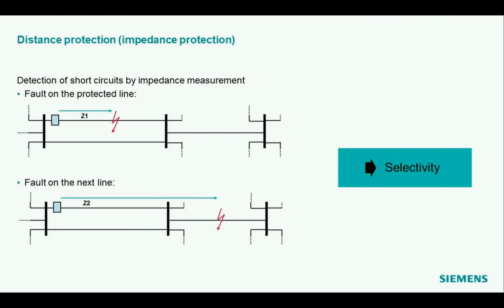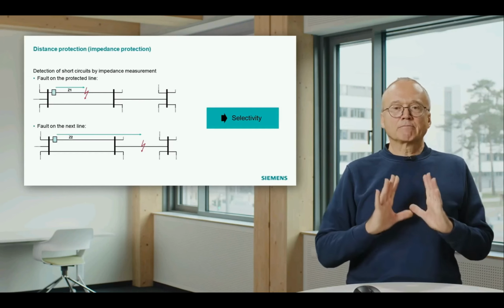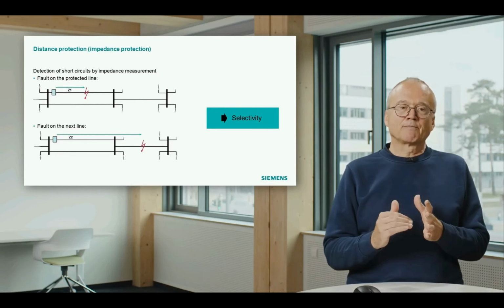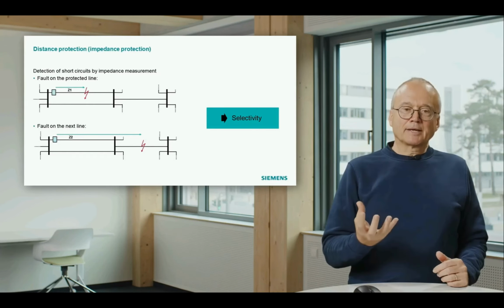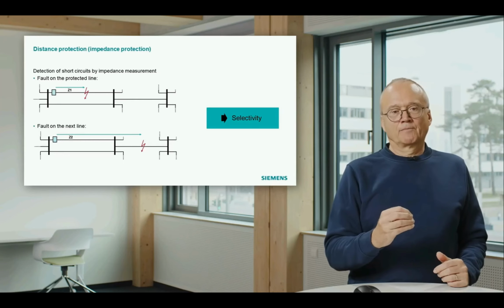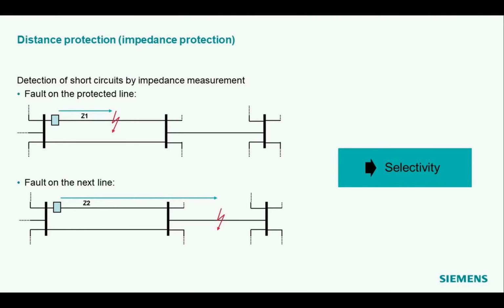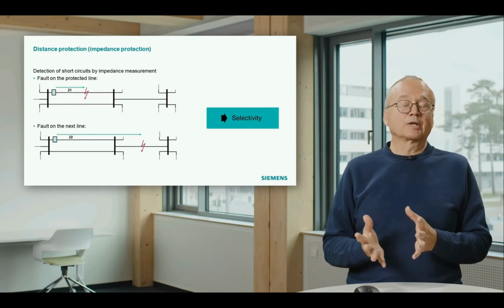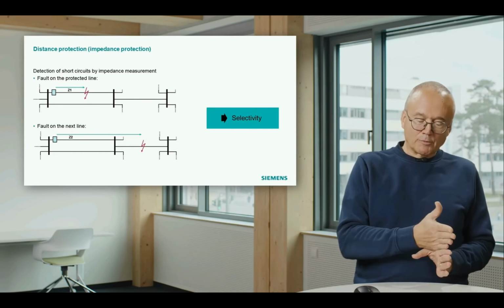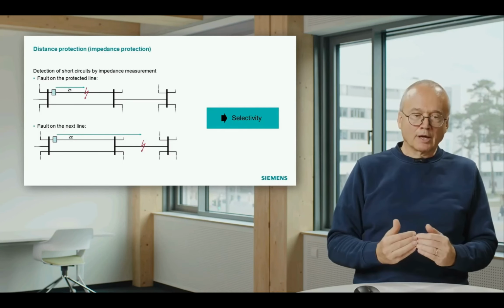This picture shows just an extract from a meshed system. And of course, in a meshed system, on beginning and end of every line, you have a protection relay with a circuit breaker. What I show here is only one of these protection relays to explain the principle. This protection relay measures voltage and current and calculates the impedance. And now it compares the measured impedance with the impedance of the line. And based on this comparison, it can decide, like in the upper part, if the short circuit is on the line, the measured impedance from the relay to the fault is smaller than the impedance of the line.